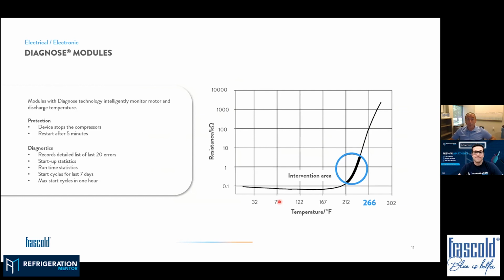Especially when components are connected in series, like between the motor and the high discharge temperature, you never understand where the alarm is coming from. By the time you try to measure after the alarm, they've already cooled down, so the resistance value is back to normal. That's why it's nice to have a device that records what really happened before.